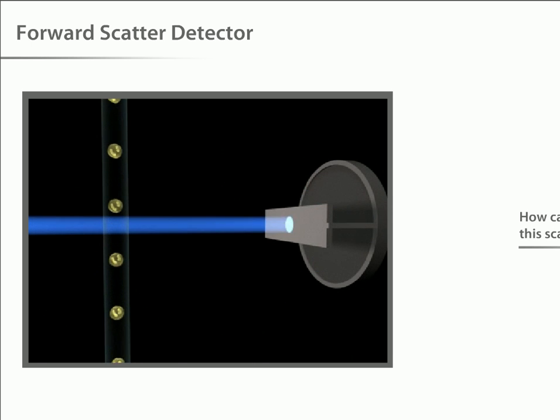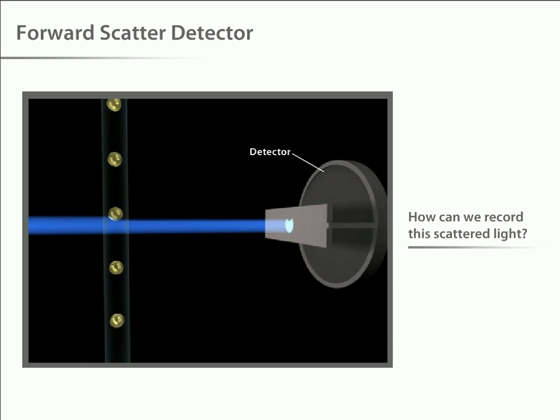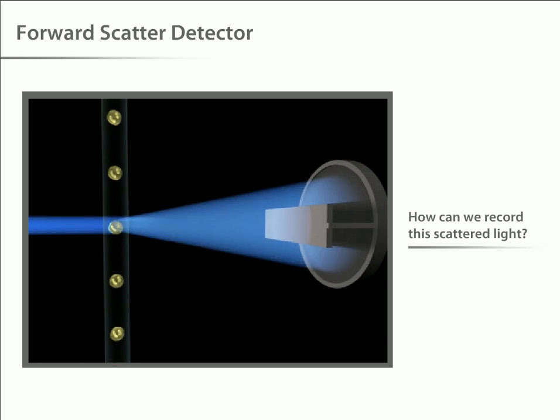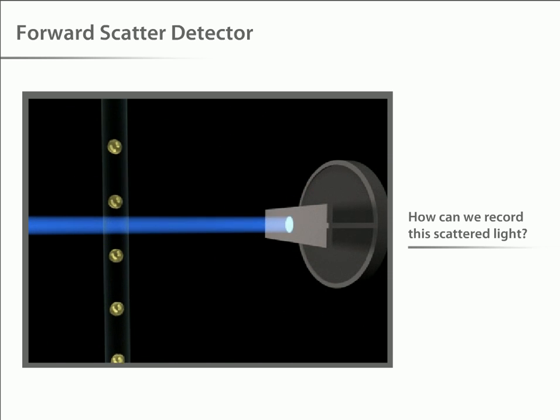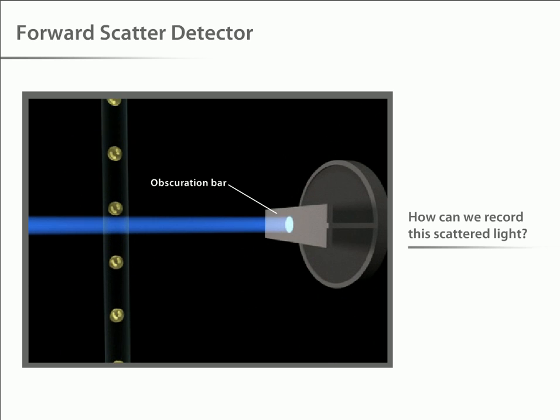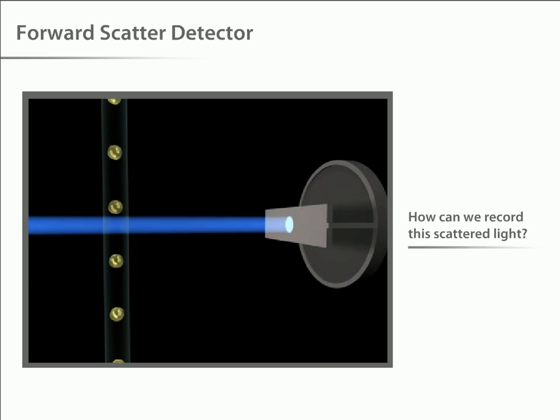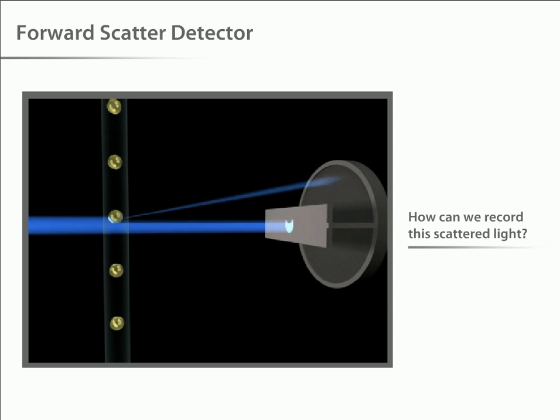But how can we record this scattered light? Light is quantified by a detector that converts its intensity into voltage. In most cytometers, a blocking bar, called an obscuration bar, is placed in front of the forward scatter detector. The obscuration bar prevents any of the intense laser light from reaching the detector. As a cell crosses the laser, light is scattered around the obscuration bar and is collected by the detector.